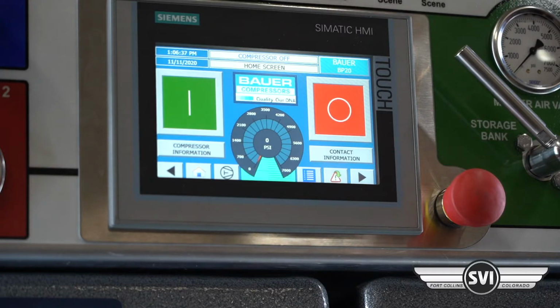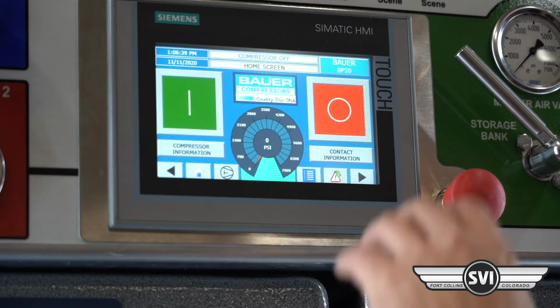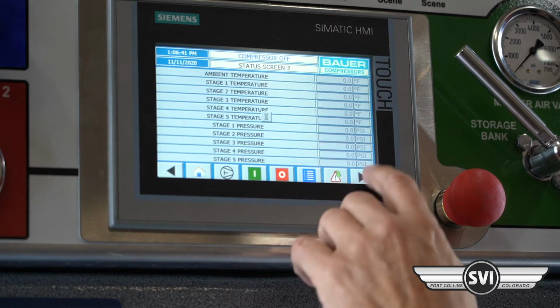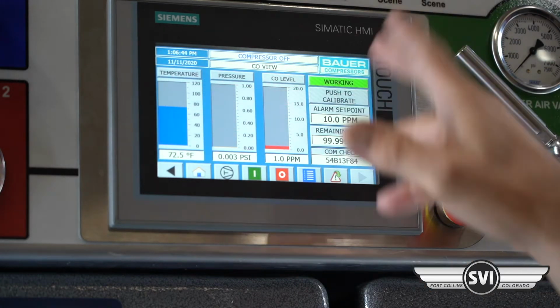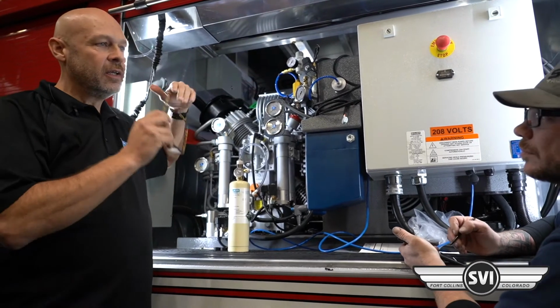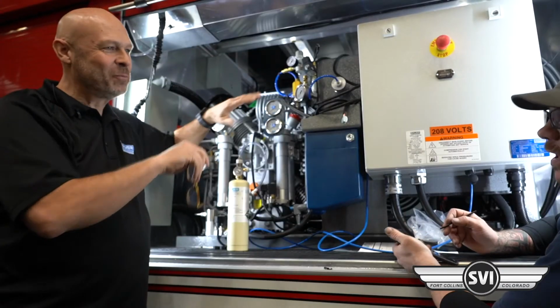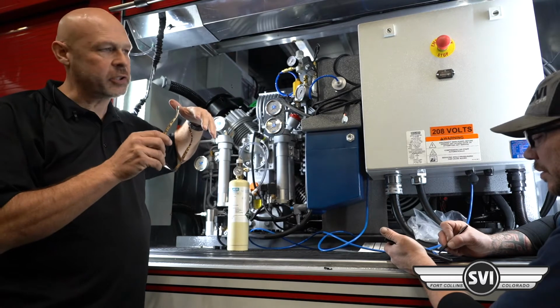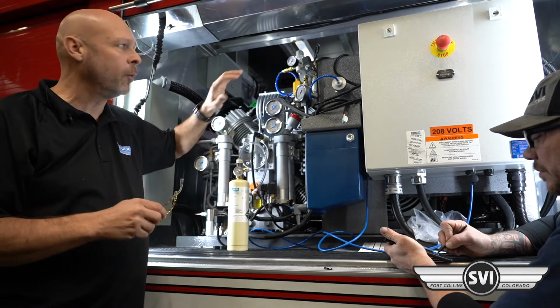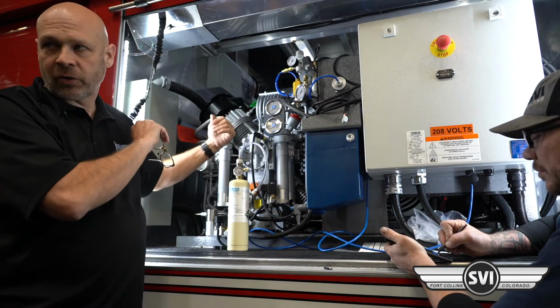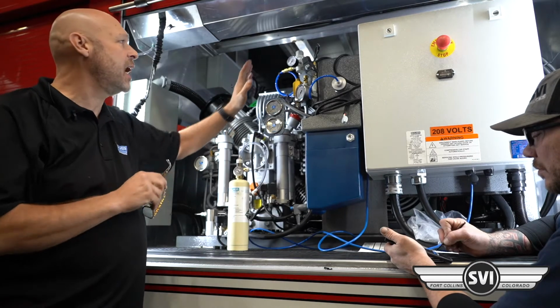Okay. So now we're going to walk through the calibration. We just arrow all the way over to calibration. When you do the calibration, the truck has to be run and you have to have it powered. You want it to run through that initialization, so at least a couple minutes warm up. But you don't want to run the compressor. The compressor is off.